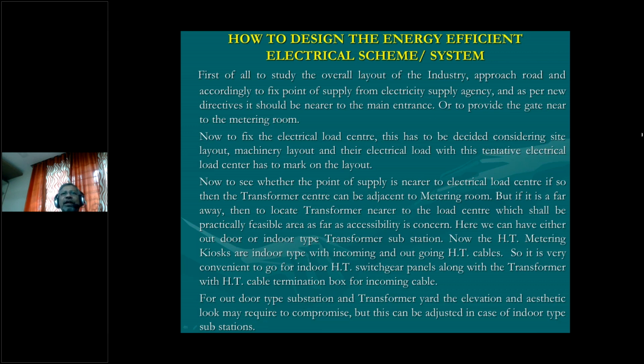Now to fix the electrical load center, this has to be decided considering site layout, machinery layout, and their electrical load. With this, a tentative electrical load center has to be marked on the layout. When we talk about mechanical load center, it is some product or some material with, say, a length of 6 feet. The center cannot be at 3 feet, because if you take a key holder, that round portion is always heavy, so your load center varies. So how do we decide load center? We try to balance it. If that object gets balanced, we say it is the mechanical load center. Accordingly, to optimize the cost, we have to calculate the electrical load center of that project.